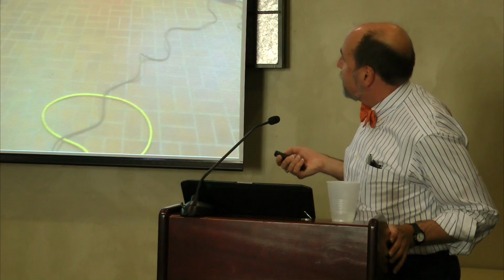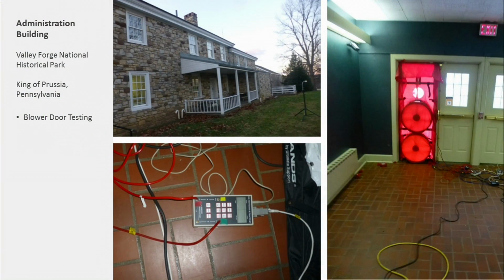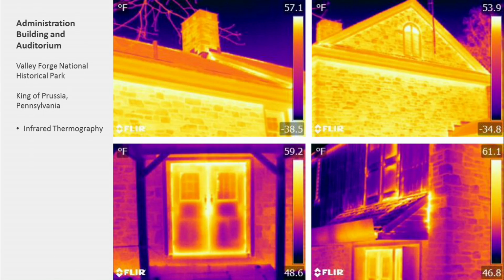Here you can see some images of their work: the blower door equipment in place, and some of their thermographic images of the two buildings. I don't think any of this is surprising—they saw significant air leakage and heat loss around openings, mostly doors. The windows on these buildings have been replaced fairly recently, so the seals and the windows themselves are fairly good, but the doors had not been, so those were an issue.